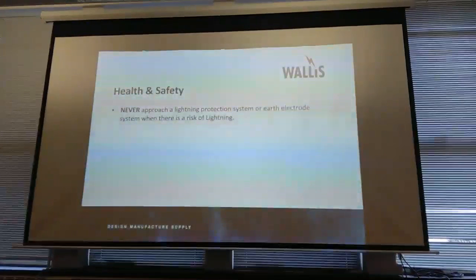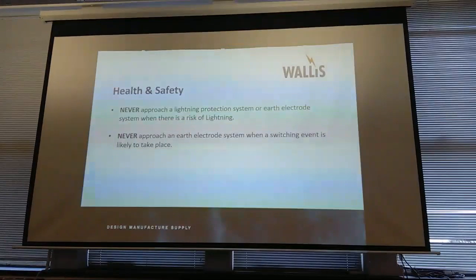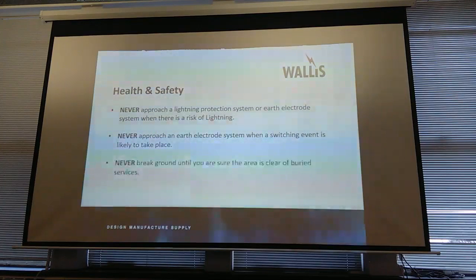Right, so we're going to run through these things again very quickly. Very much the same as lightning protection. Power earthing should be the same. Sod's Law, it's one of these things. We'll cover it off, but never approach lightning protection systems or power earthing during the risk of lightning. Reason being, if you get a strike, it's going to come up with the power system, and it will find its way through to Earth to a greater or lesser extent. And again, same with the switching event. That is when the fault is most likely to take place. Commissioning, decommissioning, switching events, that's when you likely get a fault to Earth, so don't go near it then.